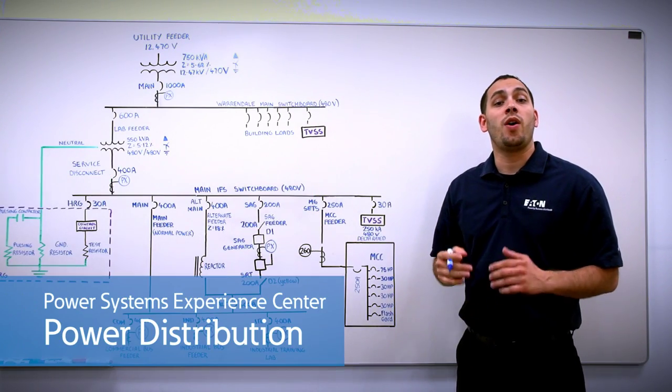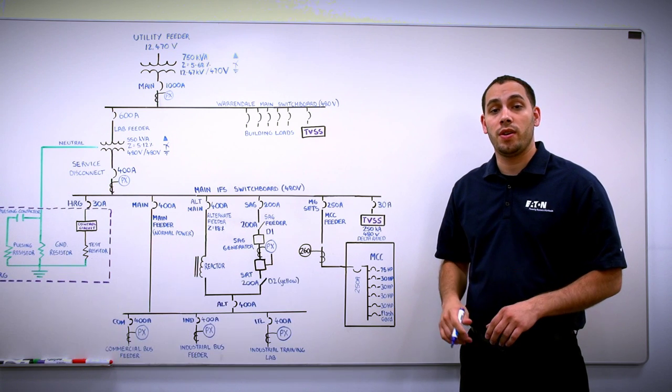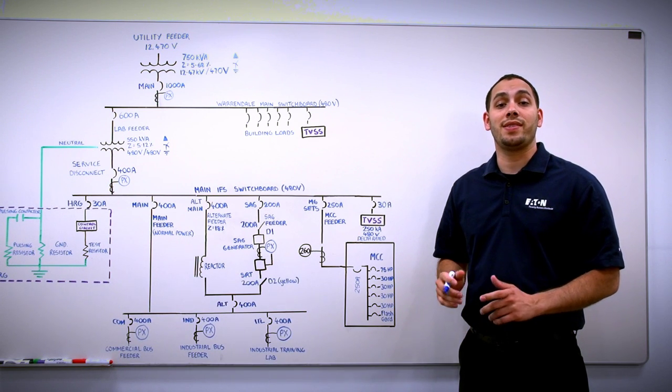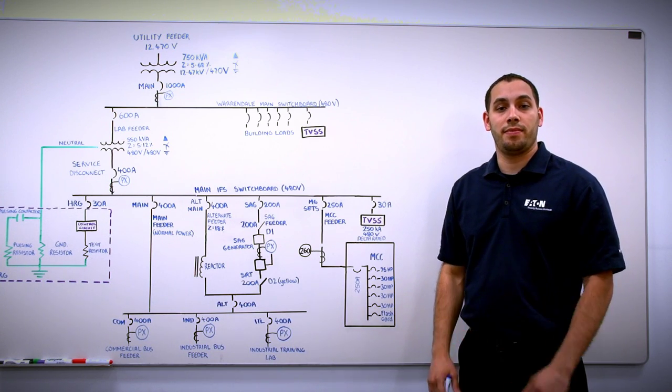Power distribution systems contain all the electrical equipment you need to safely connect a source of power to a load. These systems are scaled according to the size, type, and number of loads that are connected in the system. Behind me is the utility pole that connects our building to the city's electrical grid. This facility is fed from a 12,470-volt distribution feeder to a 750-kVA oil-filled transformer. The transformer steps the voltage down to 480 volts for distribution inside the facility.